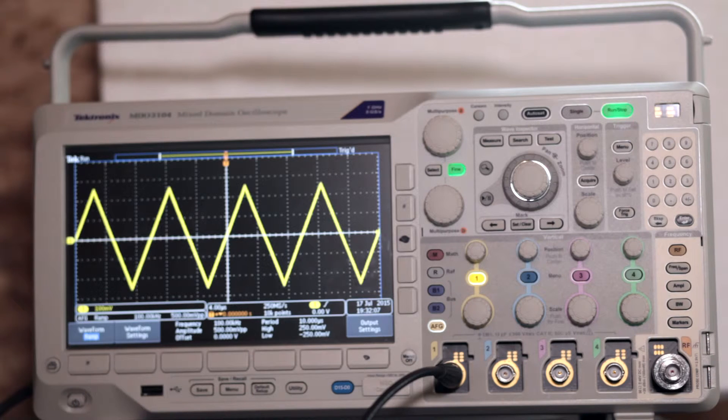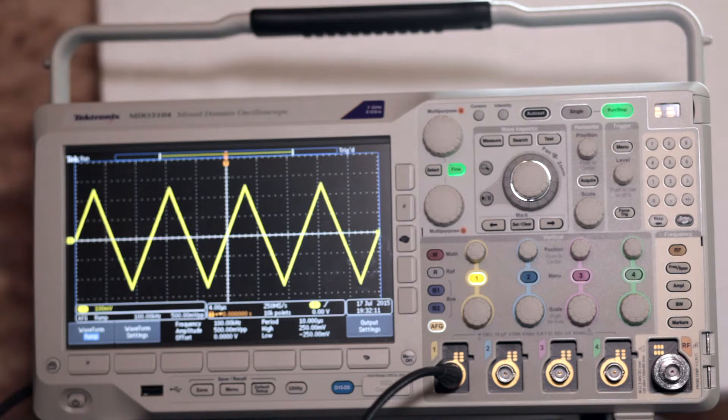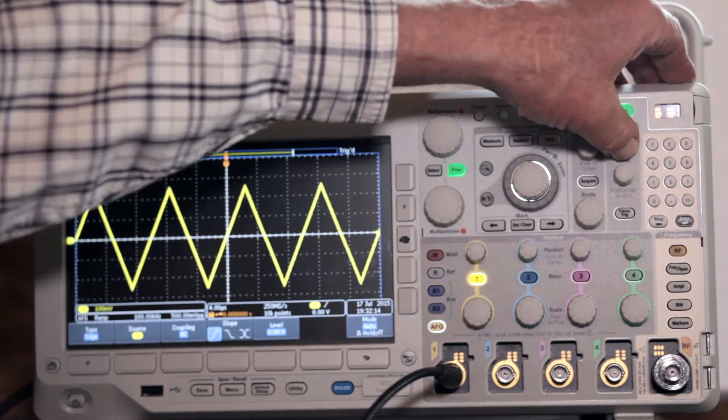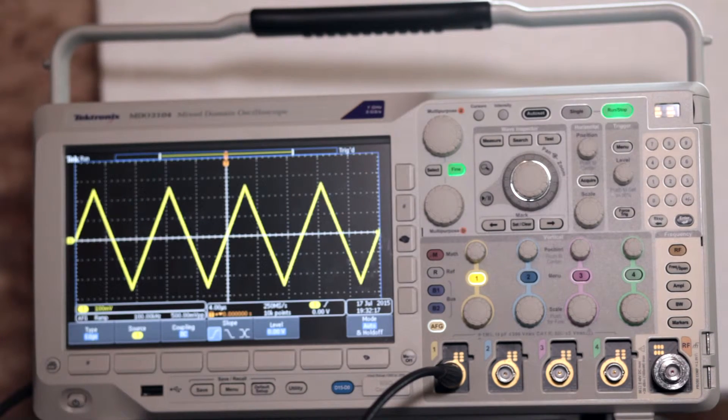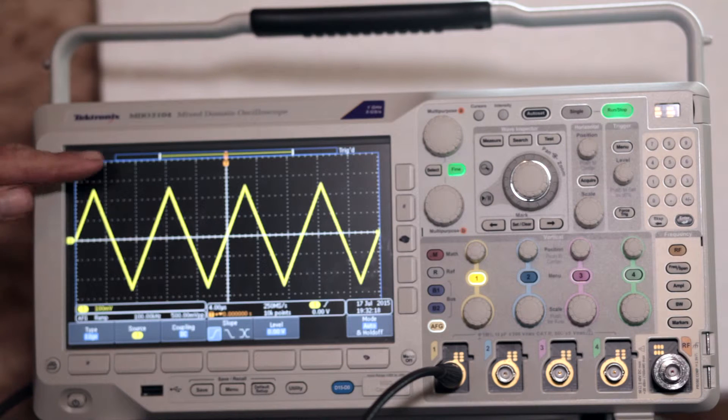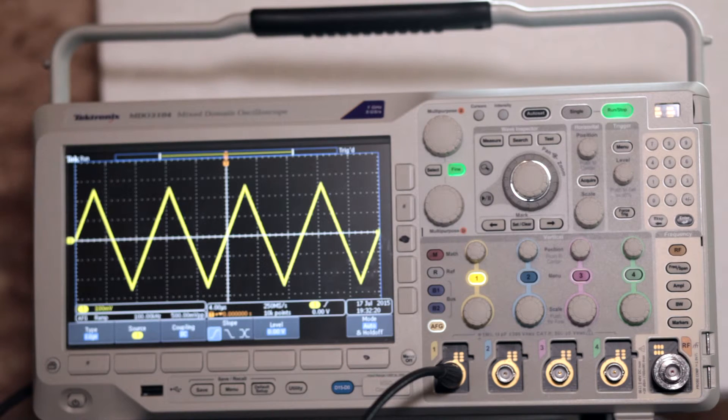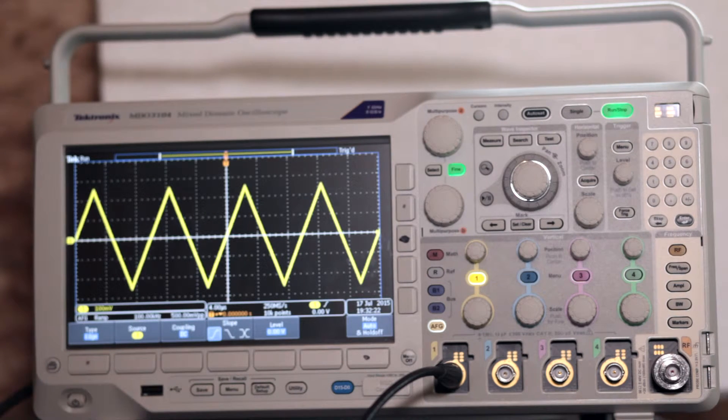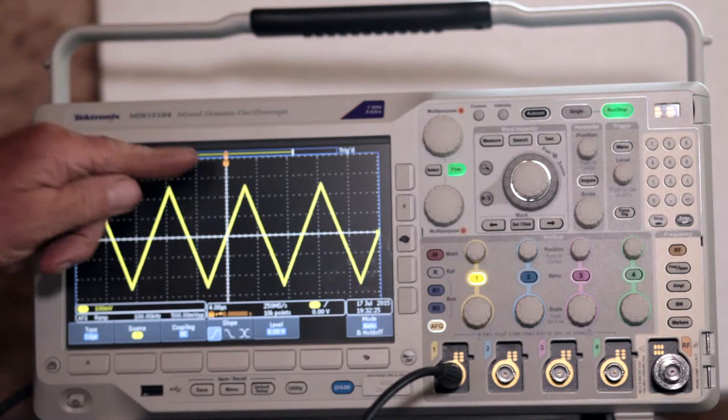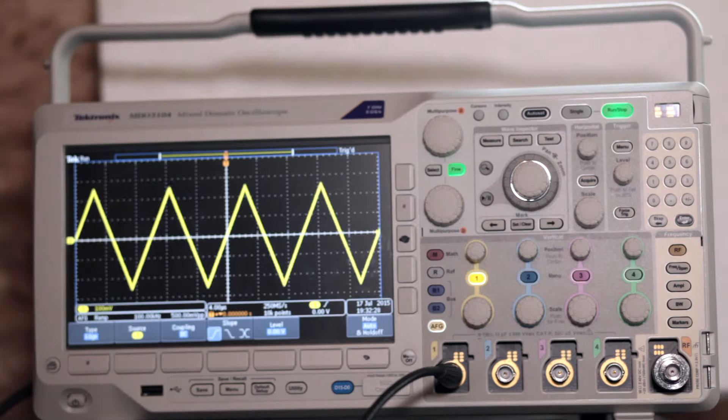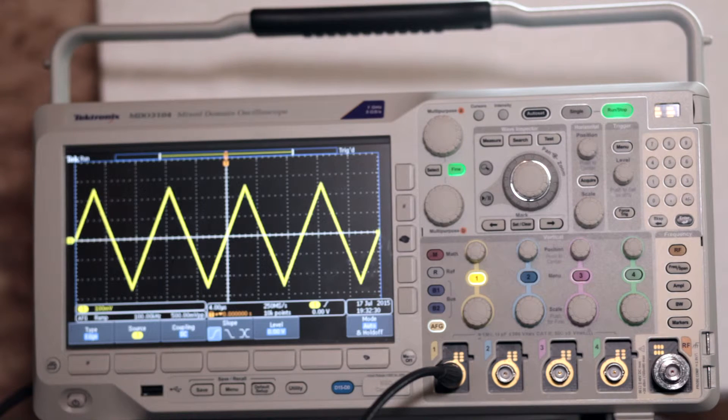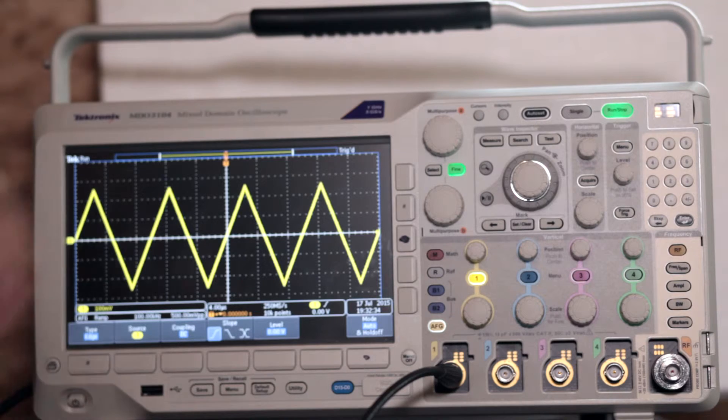In the column of trigger controls, just to the left of the keypad, press the trigger menu button. Notice the horizontal bar at the top. The icon labeled T shows the location of the trigger point. As you turn the level knob in the triggering section, the trigger point changes with respect to the Y or amplitude axis.